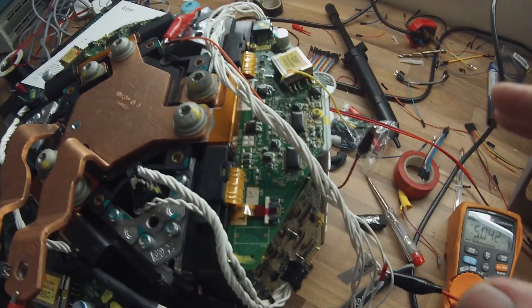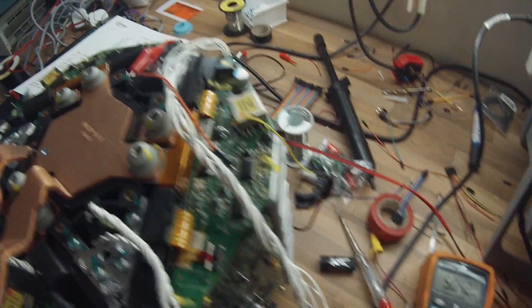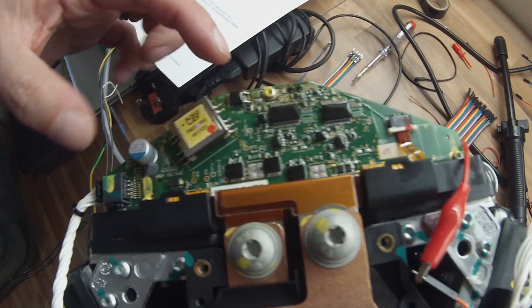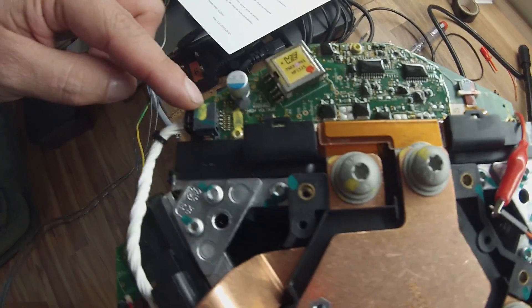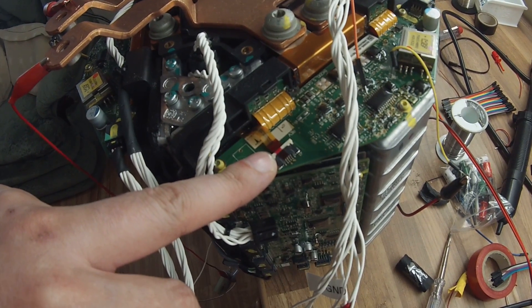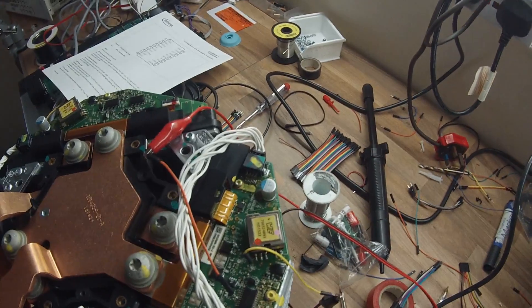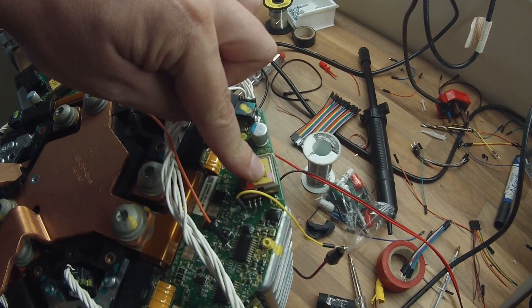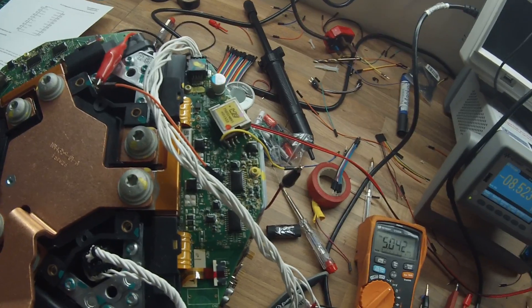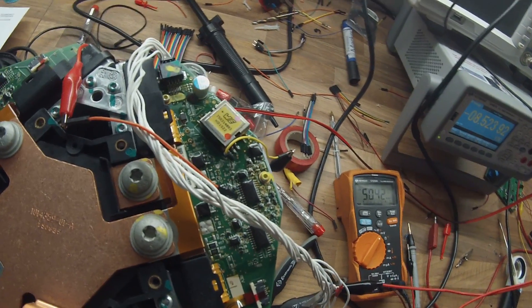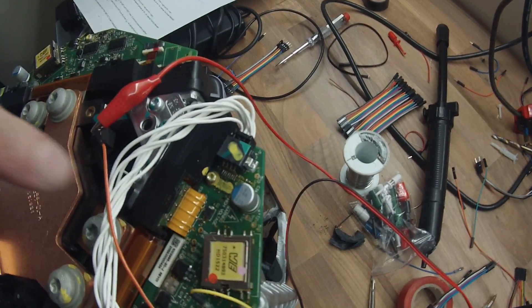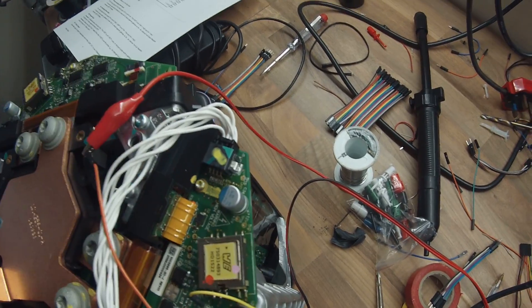I'm sorry about all the wiring here, but everything's really delicate and I don't want to move it. But you can probably see it better on this board. There's two, there's one nearest the connector. It's the high side and this one here is the low side. There's also what I suspect to be a temperature sensor connecting into each of the transistor blocks. So there's also a DC to DC converter on here. This is the transformer for it. And it provides the high and the low side isolated voltages. There are some driver chips and so on on the back. So also here is a test point for a 12V, a 5V and a ground.